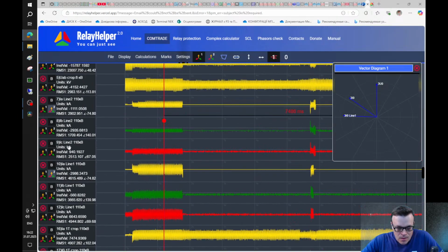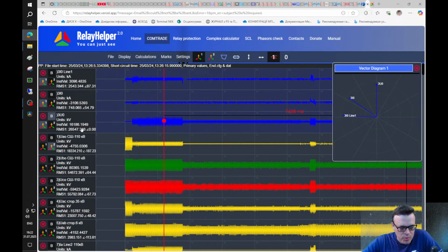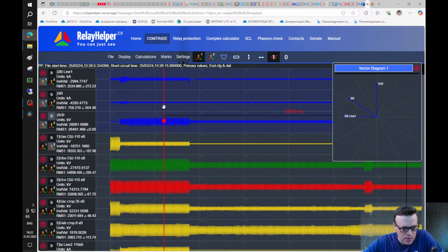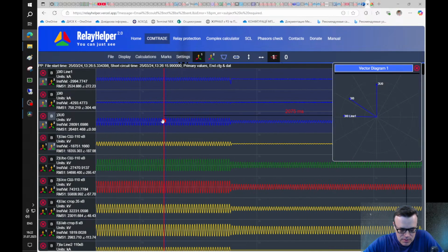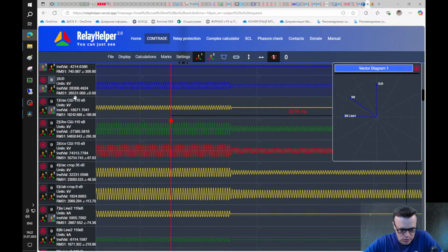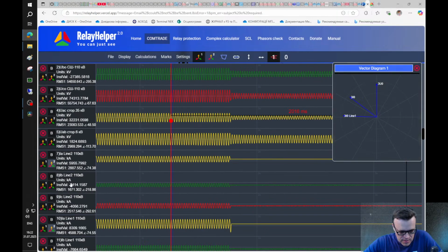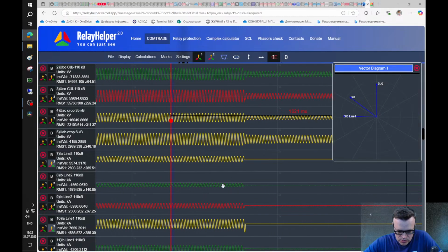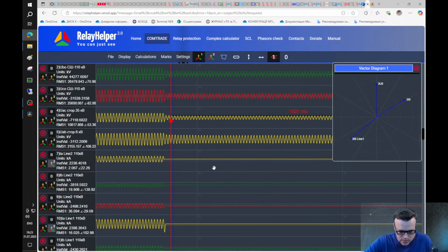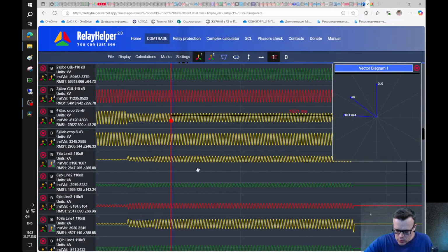Okay. So the problem is now that I don't understand why on this line 2 we have so little zero sequence current. The amount should be the same as line 1, like about 2 kiloamperes. Okay, I see that we have some problem with this channel because you see that they are shifted from the 0 point. Here the instantaneous value is about 2 kiloamperes. I don't remember that, but we can filter it.